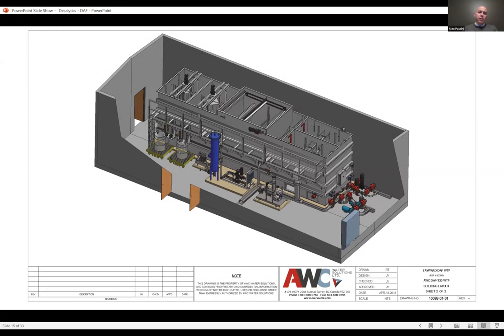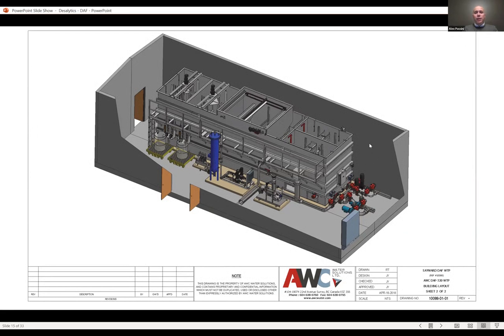Reduced footprint is important. What was very unique in this case is they didn't have any redundancy requirements. However, in order to operate the unit and do proper backwash on filters, the filter is actually cut in half — there's a dividing wall. So you can backwash each side of the filter module without interrupting total supply. The branch is set up with the proper valves and connectors to do continuous 24/7 operation in spite of any backwashing.